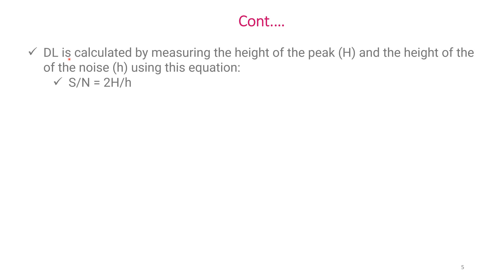The question is: how is DL calculated and how is the S/N ratio calculated? DL is calculated by measuring the height of the peak (capital H) and the height of the noise (small h) using this equation: S/N = 2 × (height of the peak) ÷ (height of the noise).